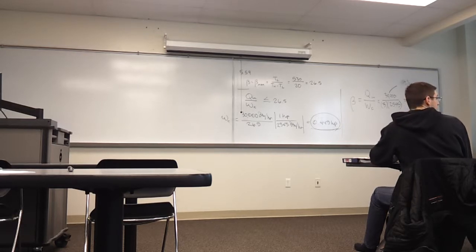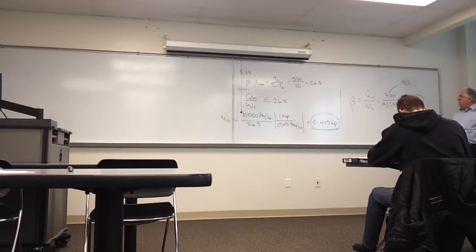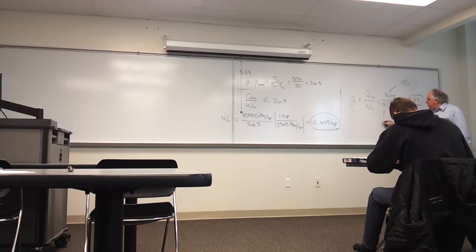So if we did the actual data and... That's the actual beta. Yes, but if we found that was greater than 26.5, then it would be not sufficient, and we would have to take a horsepower that was greater. So if the inventor said, I could do it with a 1/4 horse compressor, you would put a 1/4 horse in here, and the number would be greater than 26 and a half, and you'd say no.